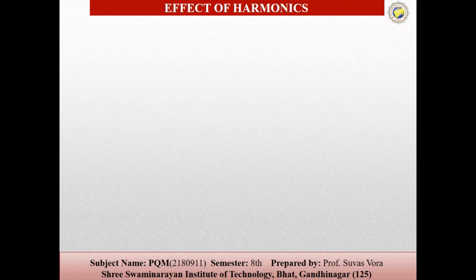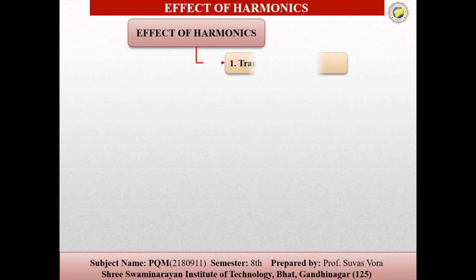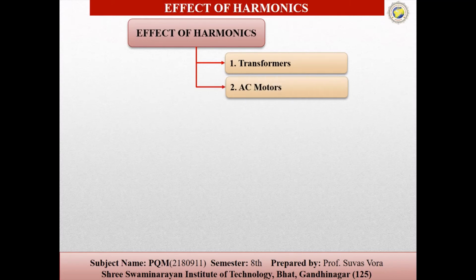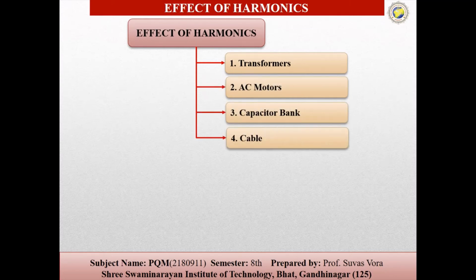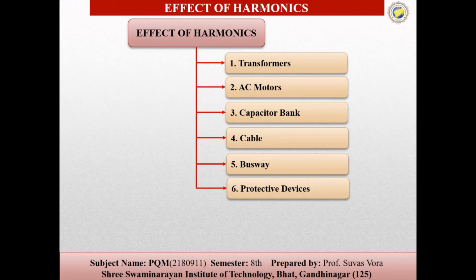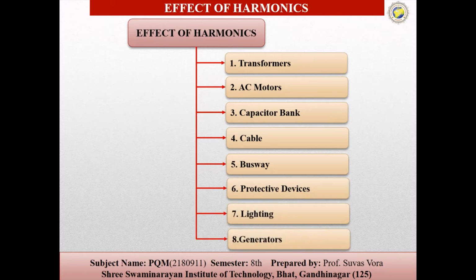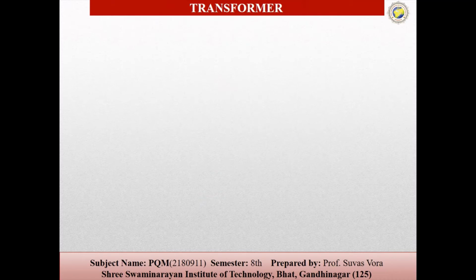So as we are interested in the harmonics, we need to find the causes of the harmonics, and until the equipment tends to malfunction, we are not aware of the harmonics. Some harmonic effects are on transformers, AC motors, capacitor banks, cables, bus bars, protective devices, lighting and generators. So now transformers. Transformers are affected by harmonics in the following ways.